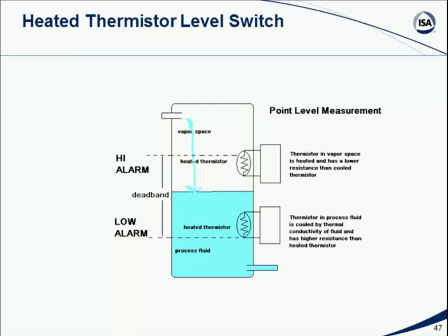So here we're kind of showing that. So I could put one of these up at the top end of the tank where we don't want to go above, and something down at the bottom level of the tank where we don't want to go below, and give me 2 point measurements that are essentially just an indication that says fluid level is below this point or fluid level is above this point. And if I don't care about the absolute level in the tank, just making sure it doesn't go below the low or doesn't go above the high, then these 2 sensors would be adequate. And again, these are point sensors, so they're really generating a contact signal, not an analog signal. They're not continuous reading. It's contact that says, yes, the fluid level's at this level or above, or no, it's got to be below me. Okay?